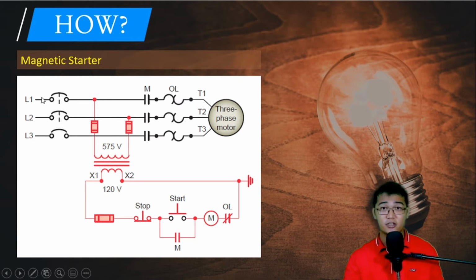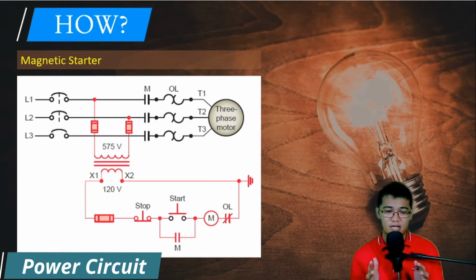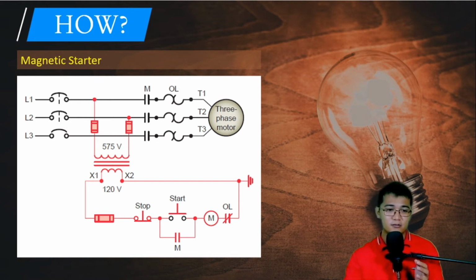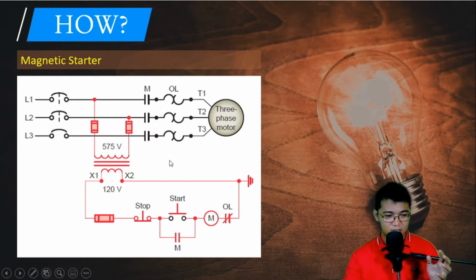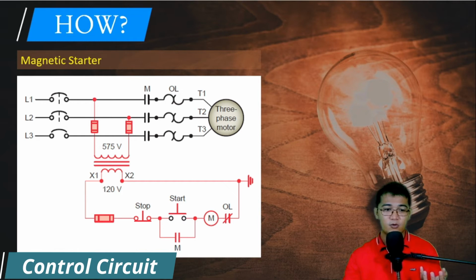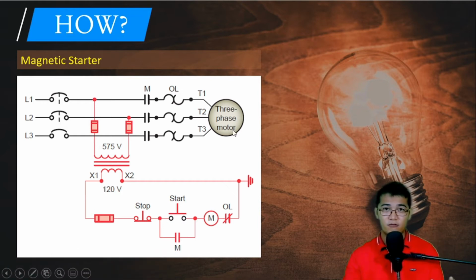We notice here that we have two circuits: the one colored black on top, and the one colored red at the bottom. We call the circuit on top the power circuit, the circuit where our load is connected. In this case, our load, what we want to run, is our three-phase motor. Again, the power circuit is the circuit where our load is connected. And the one colored red, we call this the control circuit. This means we can manipulate, we can turn our load on or off depending on this particular arrangement on the control circuit. So let's see how this magnetic starter functions.